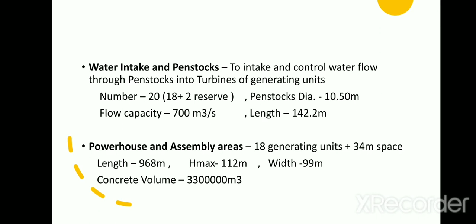Moving on, we had the water intake and penstocks. These are used to intake and control water flow through penstocks into the turbines of the generating units. These are 20 in number, with 18 working and 2 in reserve. We have penstocks with a diameter of 10.5 meters, a flow capacity of 700 meter cube per second and a length of 142.2 meters. Now we have the powerhouse and assembly areas with 18 generating units having 34 meters space in between, with length, maximum height, width and concrete volume being given.